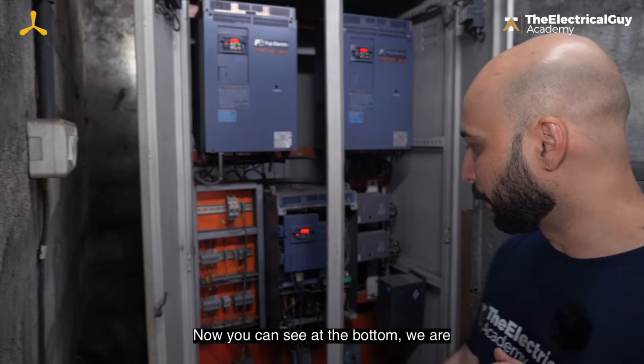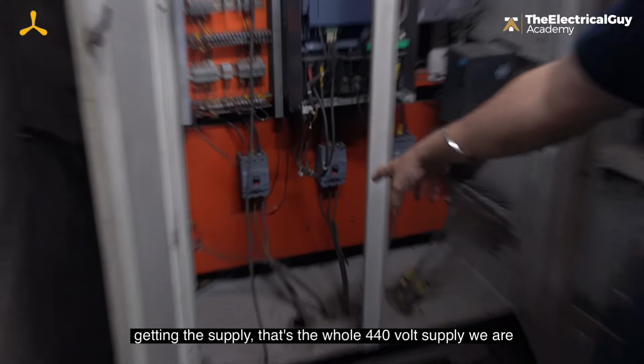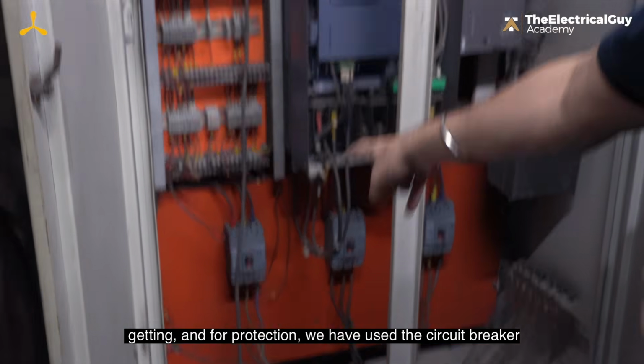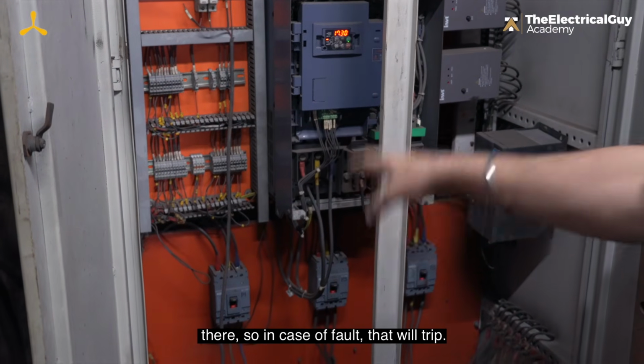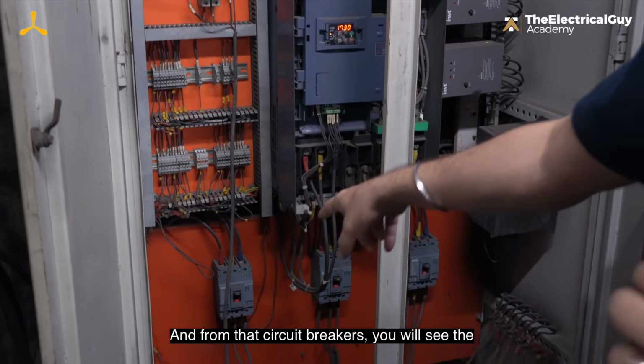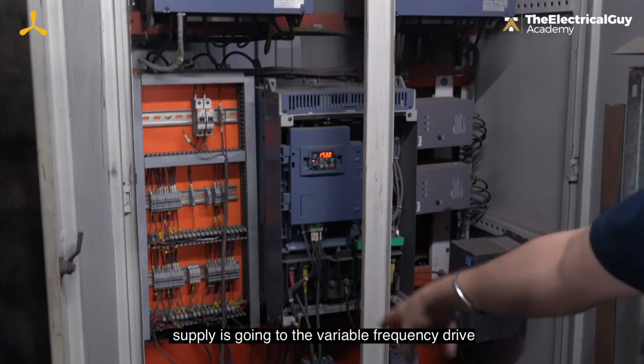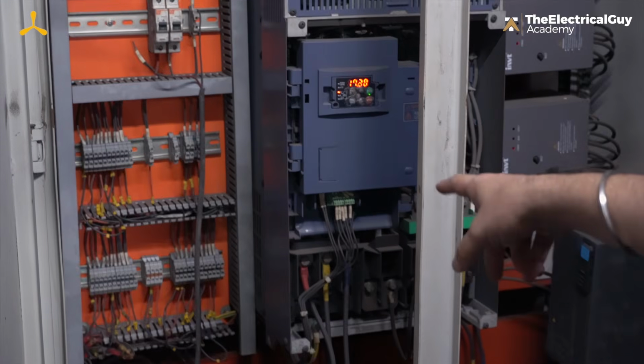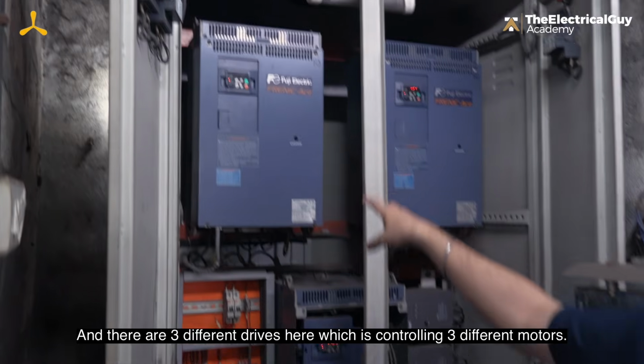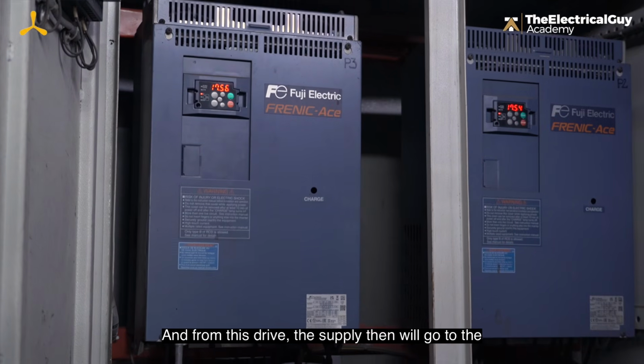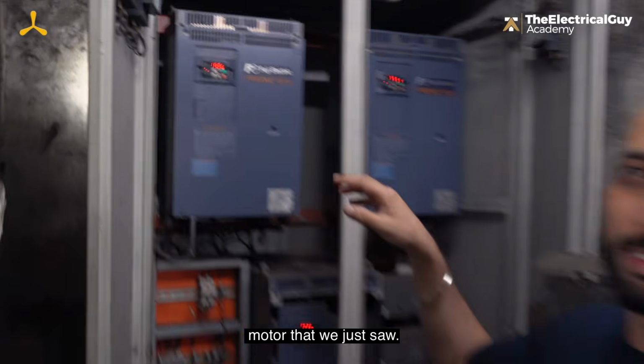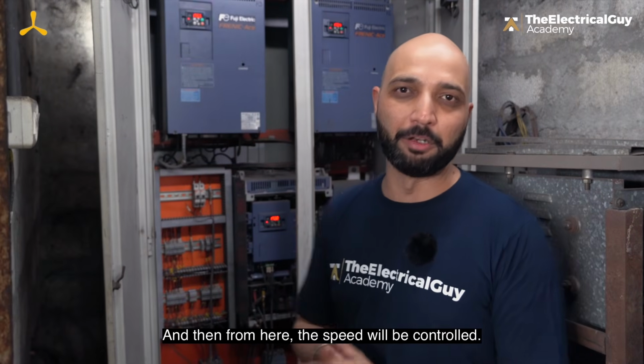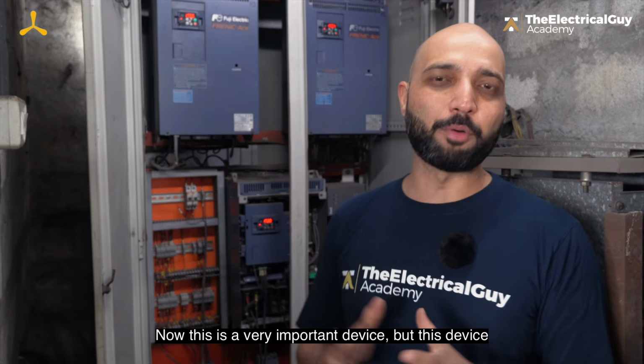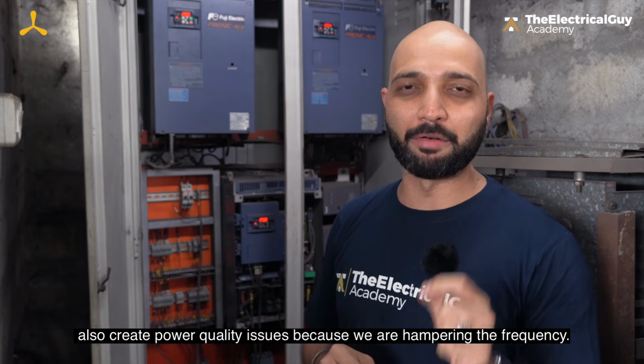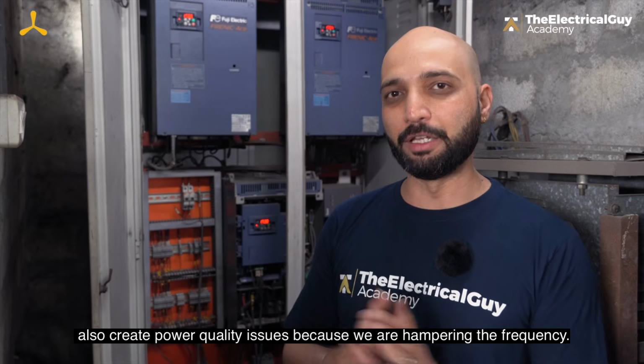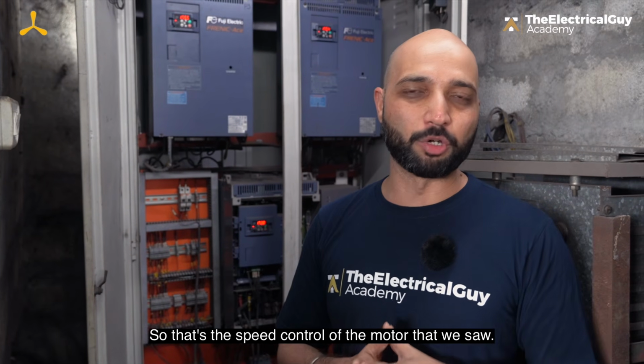Now, you can see at the bottom, we are getting the supply. That's the 440 volt supply we are getting. And for protection, we have used the circuit breaker there. So in case of fault, that will trip. And from that circuit breaker, you will see the supply is going to the variable frequency drive. And there are 3 different drives here, which are controlling 3 different motors. And from this drive, the supply then will go to the motor that we just saw. And then from here, the speed will be controlled. Now, this is a very important device, but this device also creates power quality issues because we are altering the frequency. So that's the speed control of the motor that we saw.